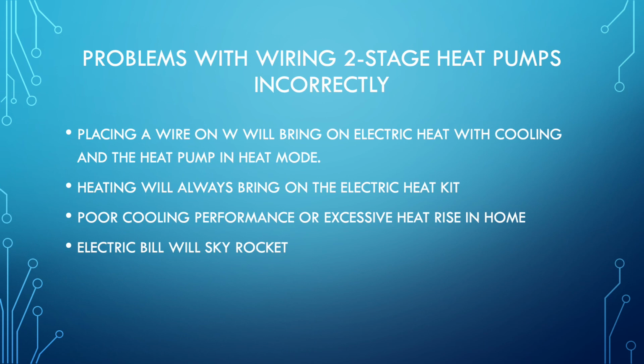It'll also cause excessive heat rise in the home, where they just kind of have this runaway heat, because of the way the sequencer timer is set up inside the air handler on particularly Rheem equipment. If you have a wire on W, it can force the electric heat kit, once energized, to now stay energized even after the system should have turned off. So what you end up with is a homeowner calling and saying, hey, it's 90 degrees in my house, the thermostat's set for 75, it's wrong. And we tell them to go cut the breaker if that's the case. We haven't really run into this, but that is a symptom of what you'd be looking at.